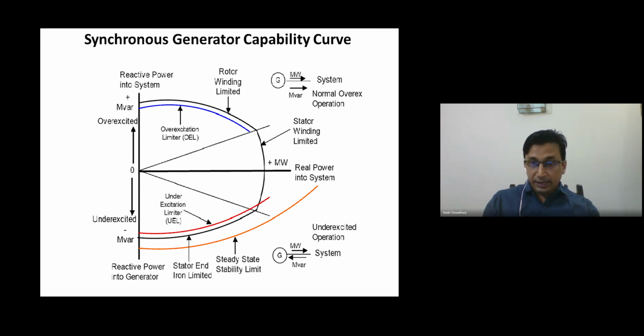If you follow my cursor on this curve, megawatt, that is the stator winding limit. So up to that limit, we can produce megawatt.